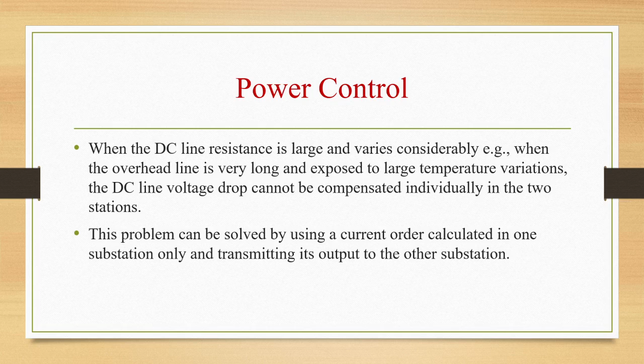To get equal calculated current orders in the two stations, measured DC line voltage must be referred to the same point on the DC line by compensation for DC line voltage drop. This will be done by adding the term plus or minus R into ID to the measured voltage, thus referring the voltage to a common reference point.